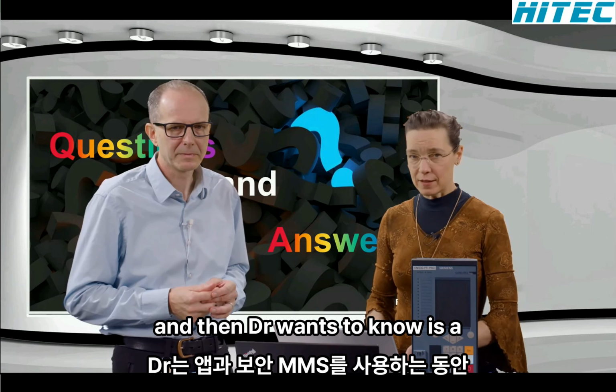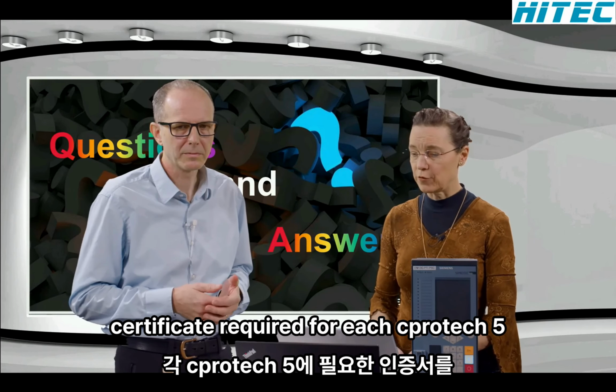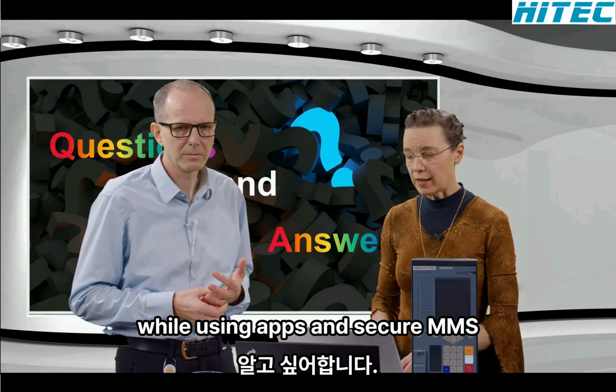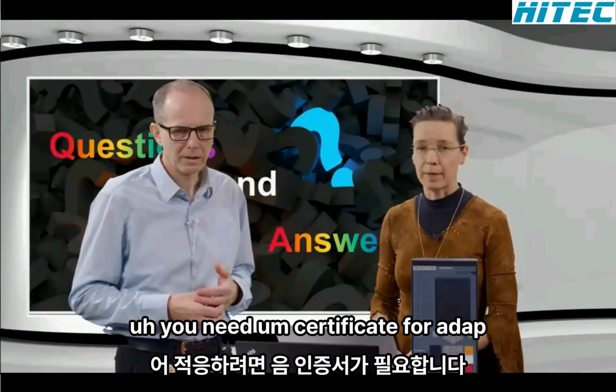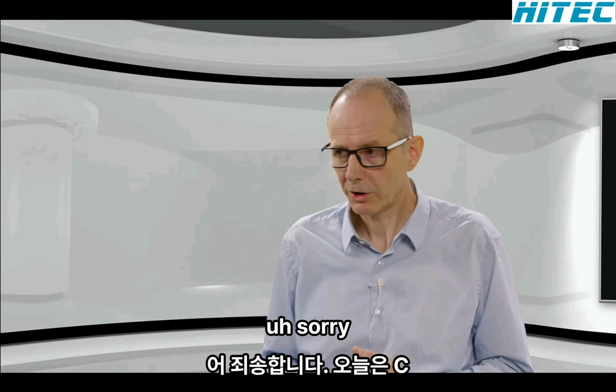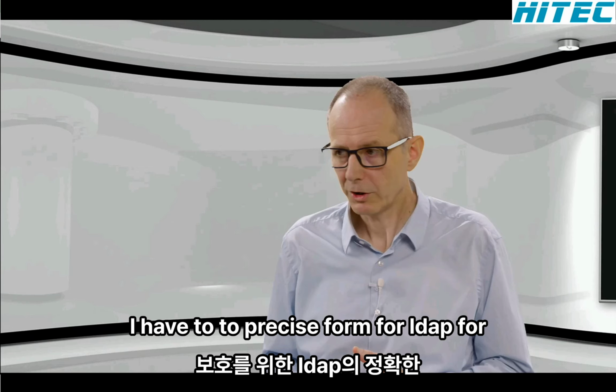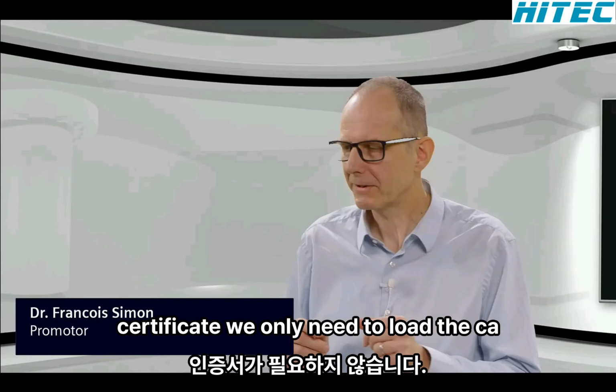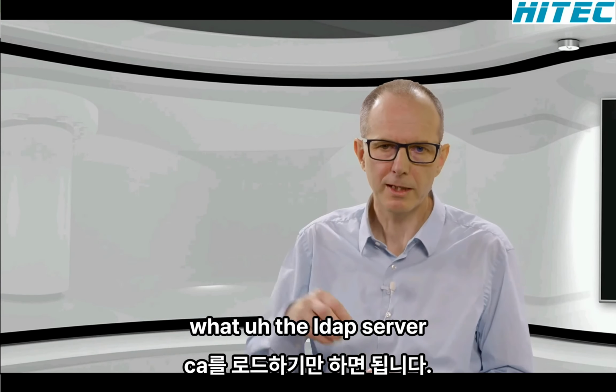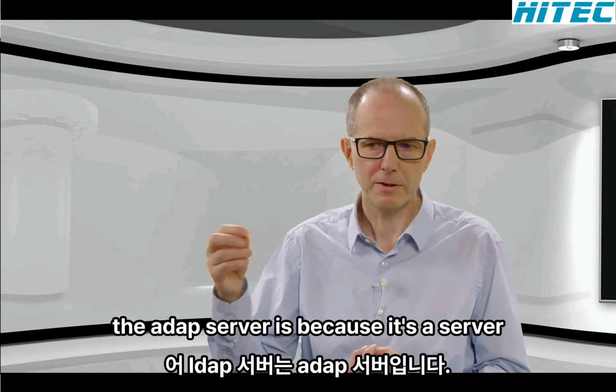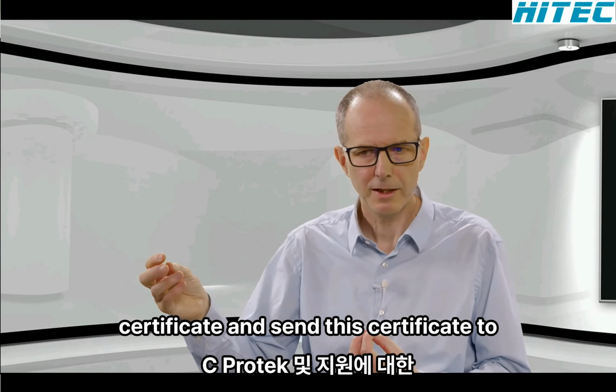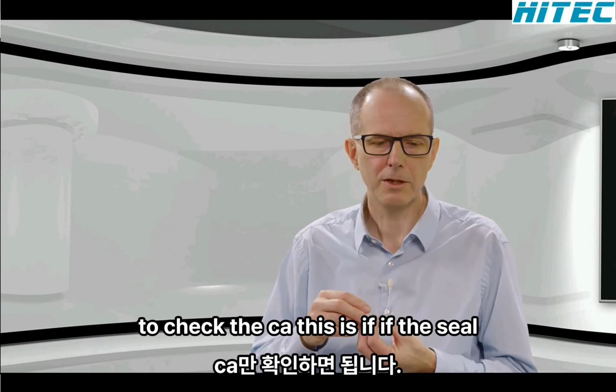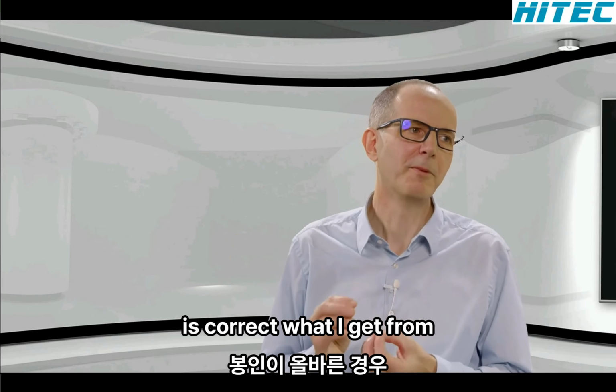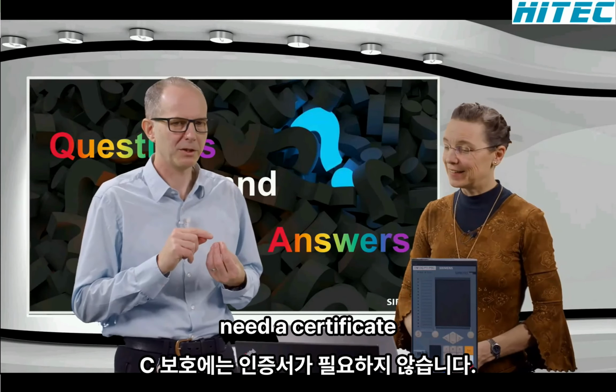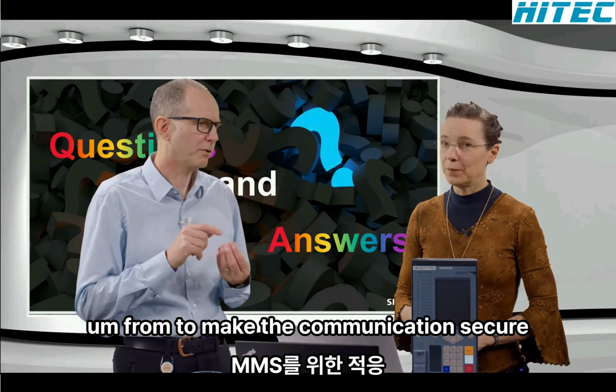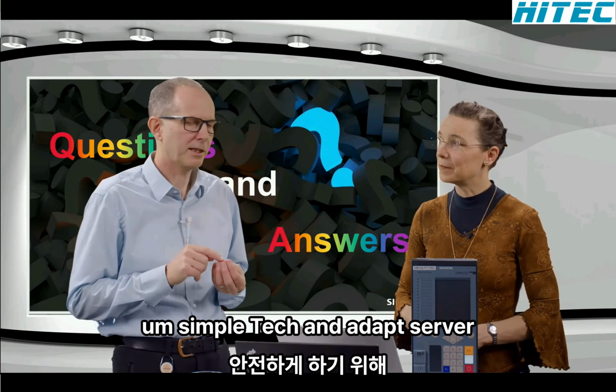And then DR wants to know, is a certificate required for each SIPROTEC 5 while using LDAP and secure MMS? You need a certificate for LDAP. Sorry, I have to be precise. For LDAP, for the SIPROTEC today, we do not need a certificate. We only need to load the CA of the LDAP server. Because it's server authentication, the LDAP server has a certificate and sends the certificate to the SIPROTEC, and the SIPROTEC only has to check the CA, if the seal is correct, from what I get from the LDAP server. So SIPROTEC does not need a certificate to make the communication secure between SIPROTEC and the LDAP server.